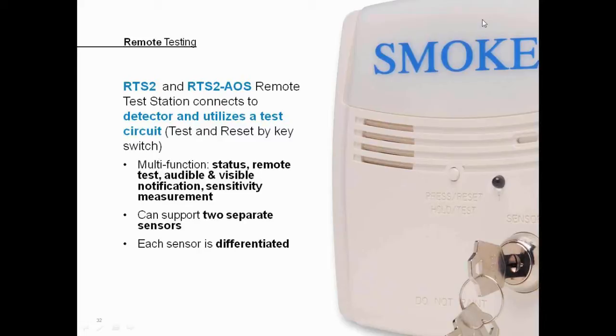They provide remote testing that can be conducted via the test button that mimics the test button on the detector housing as well. And it has the ability to perform detector sensitivity testing from a remote location. We'll talk a little bit more about the sensitivity testing at a later point, but one unique thing about this detector is you are able to take a sensitivity reader directly to the accessory, test it for sensitivity, and get provided a sensitivity readout of your detector in the space up in the ceiling.